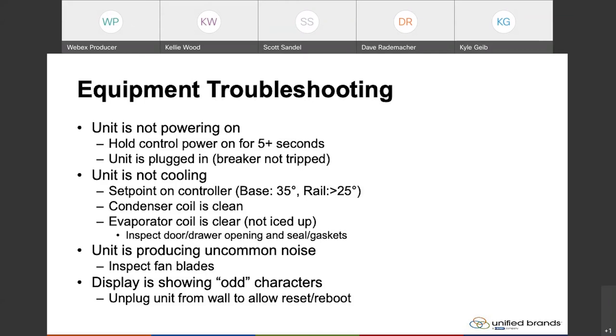One other thing to mention: when you unplug the unit from the wall and re-plug it back in, the unit will start in a defrost mode. You will see DEF on the controller. That's a mechanism we built into the units purposely — so if the unit stops running because the coil senses that it has iced up, it'll put it into defrost. If someone thinks that's happening improperly and just unplugs the unit to reset it, it automatically starts in a defrost cycle to protect itself from jumping right into a cooling cycle and damaging the components inside of the coil.